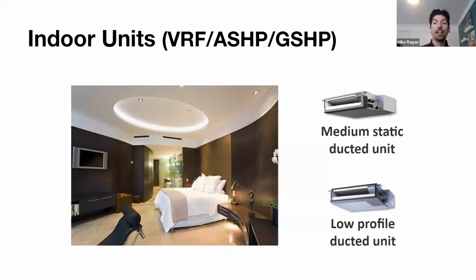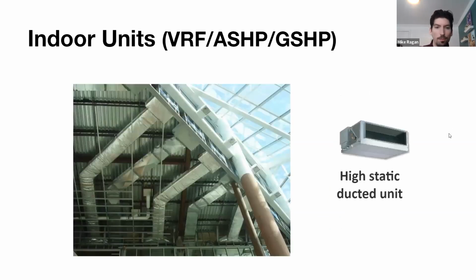And this equipment comes in various static settings. We have our low profile ducted units. Those are oftentimes a great fit for those hotel rooms with very limited above ceiling space right above the door. Those low profile units can fit right in that entryway space, and that would serve an entire unit. We have medium and high static ducted units as well, static up to about just under an inch of static for those high static situations where you just have one single unit serving a very, very long length of ductwork. That's an option as well. Here's an example of such a high static unit, and it showcases just how much ductwork we could put off of one of these units.